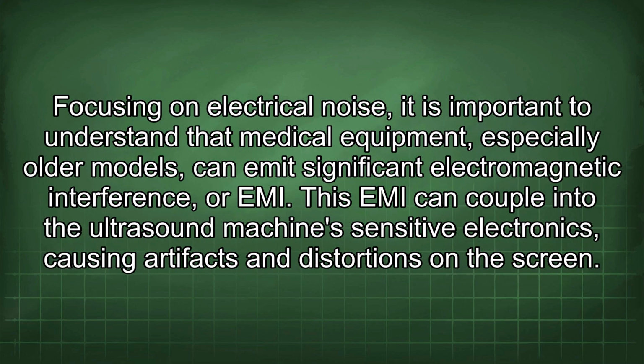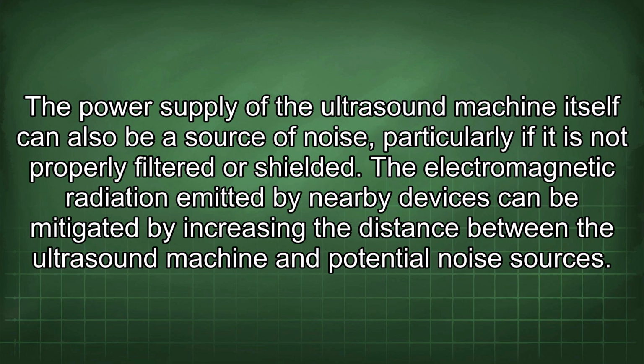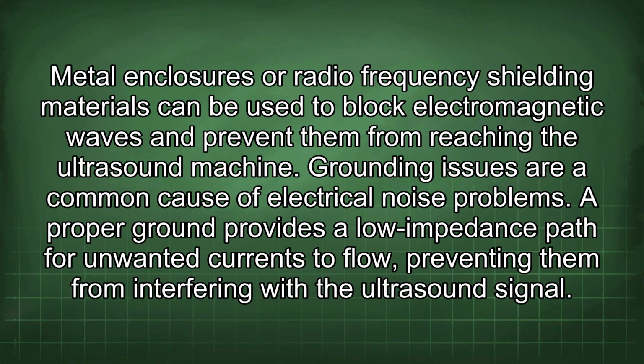Focusing on electrical noise, it is important to understand that medical equipment, especially older models, can emit significant electromagnetic interference or EMI. This EMI can couple into the ultrasound machine's sensitive electronics, causing artifacts and distortions on the screen. The power supply of the ultrasound machine itself can also be a source of noise, particularly if it is not properly filtered or shielded. The electromagnetic radiation emitted by nearby devices can be mitigated by increasing the distance between the ultrasound machine and potential noise sources. Metal enclosures or radio frequency shielding materials can be used to block electromagnetic waves and prevent them from reaching the ultrasound machine.